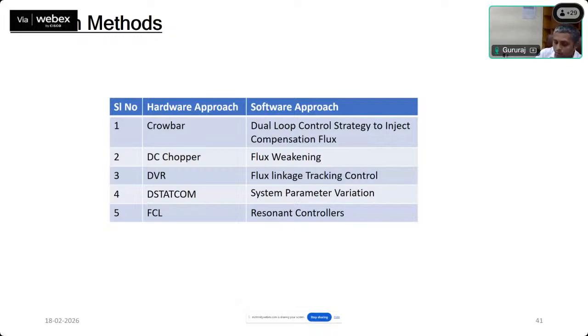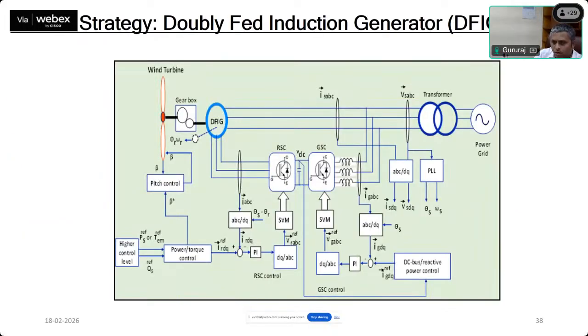And then another important solution methodology that is quite researched in the area of low voltage ride-through capability enhancement of a DFIG is the implementation of a fault current limiter. So the fault current limiter is placed. A fault current limiter inherently is an impedance or a resistance which is offered to the system at some point of time. That means electrically, this resistance or impedance is seen whenever there is a fault, and that is connected in between the double fed induction machine and the grid.